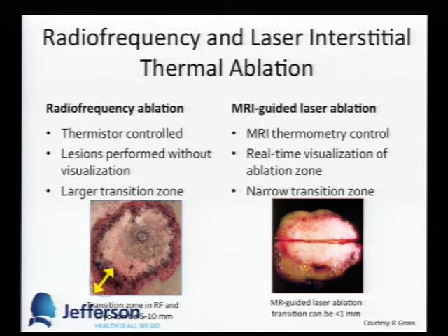So when we do this operation, where we don't want any of the burn to happen, like yesterday we did a 4-year-old girl with a hypothalamic hamartoma, we put our temperature sensors on the optic tract because we didn't want the temperature on the optic tract to ever be hot enough to cause irreversible tissue damage, right? So you can actually exactly dial in where you want it.